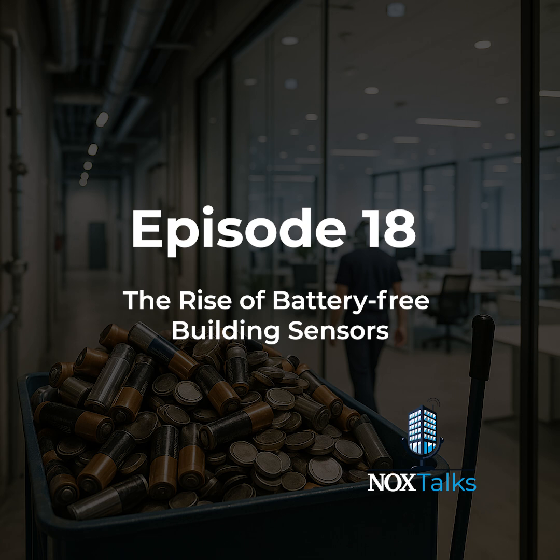These sensors still need to talk to your building management system. To keep power use tiny, they use ultra-low energy wireless standards. One example is the EnOcean protocol, designed so a single button press or a few seconds of indoor light is enough to send a message. Gateways then translate that into BACnet, Modbus, or whatever your existing BMS is already using.